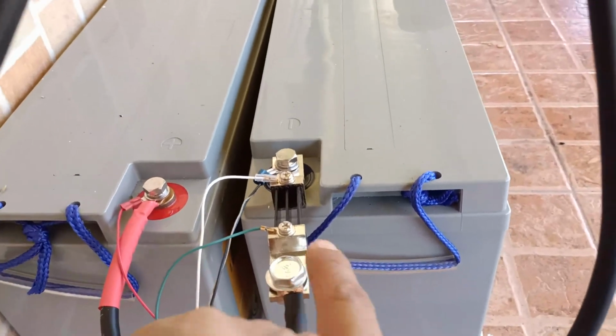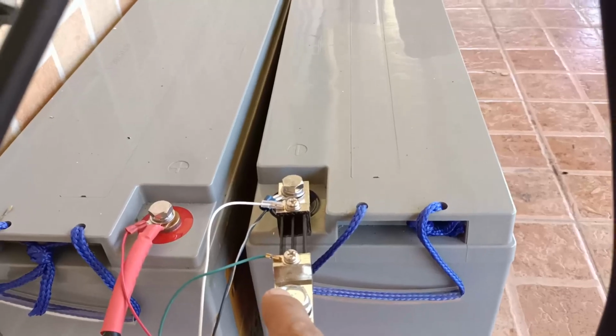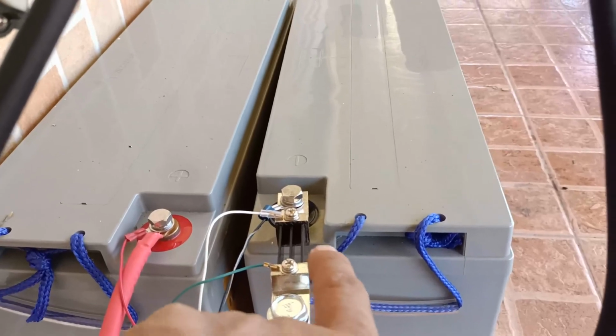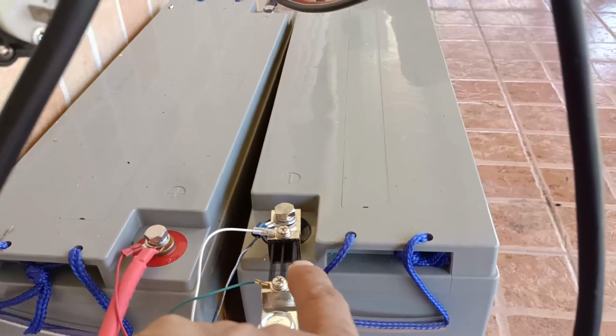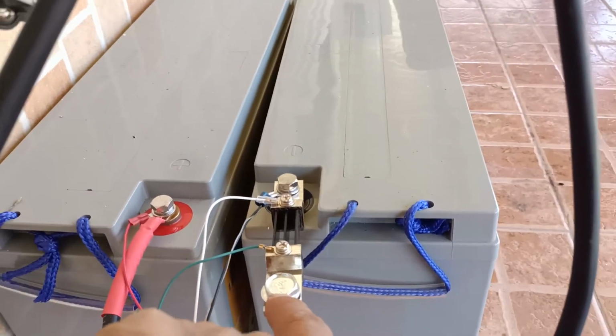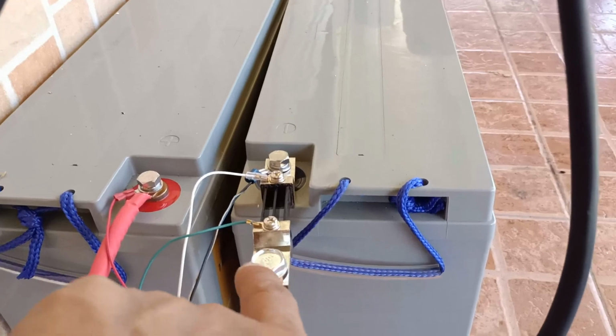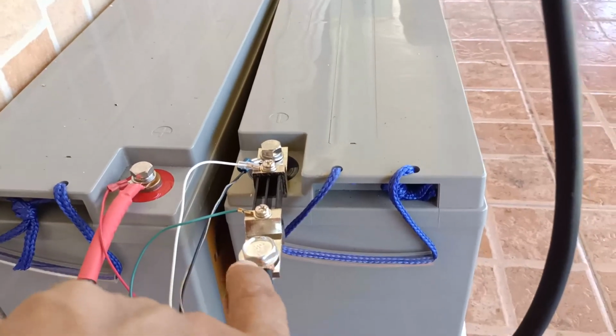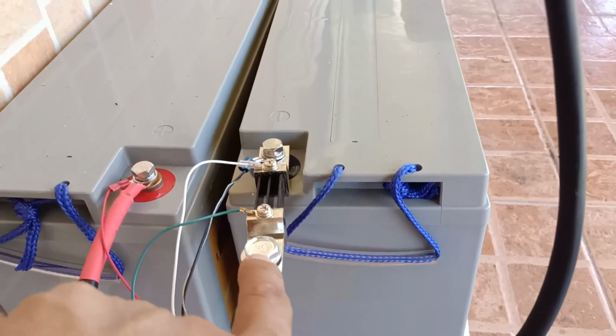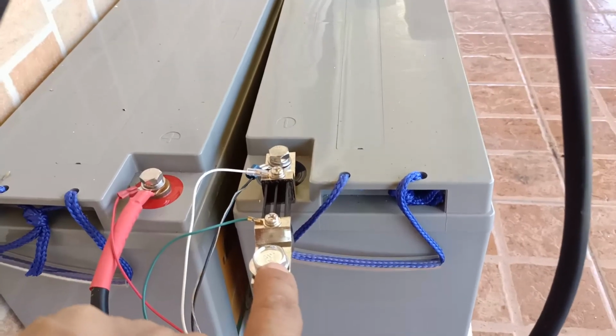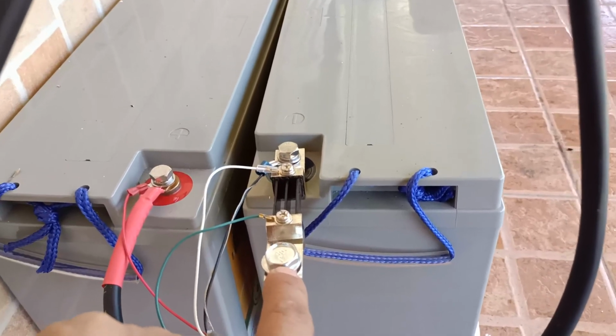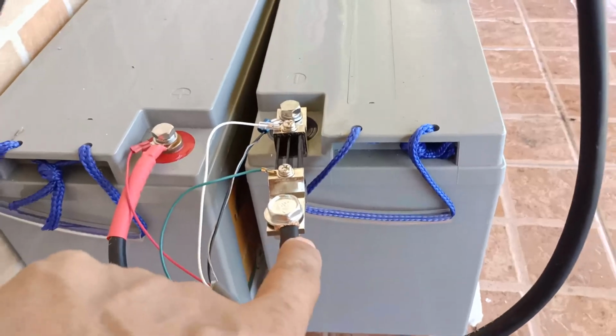This is the sensing resistance of the device. It's basically a metal resistor, laser cut to provide a certain resistance. So at 300 amps, it will have a voltage drop of 0.075 volts, or 75 millivolts.